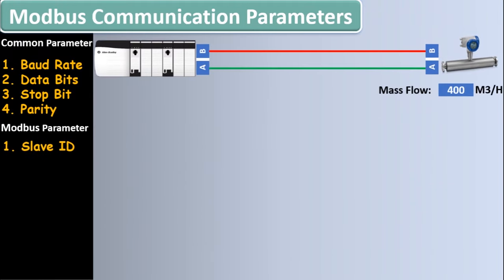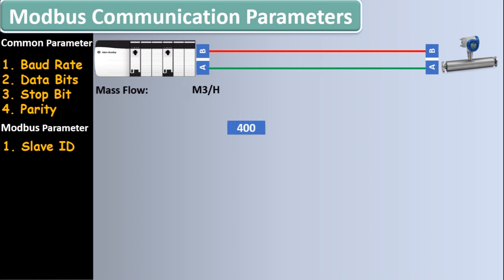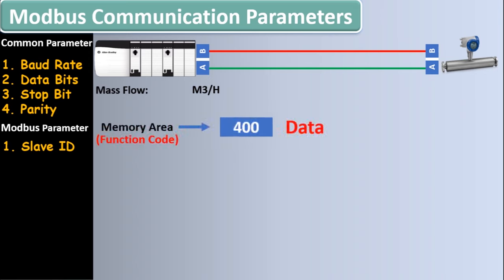All the communication parameters and slave ID along with the wiring are used to generate communication between two devices. Once the communication is generated, we are able to move data from one device to another. For example, suppose the real-time mass flow value on a flow meter is 400 cubic meters per hour and we want this data on our master device. Basically 400 is the data. This data exists on some memory area represented by the function code in Modbus parameters. Also, this data memory area has an address which we call a register. This register has some data type and data formatting — I will elaborate all these terms one by one.